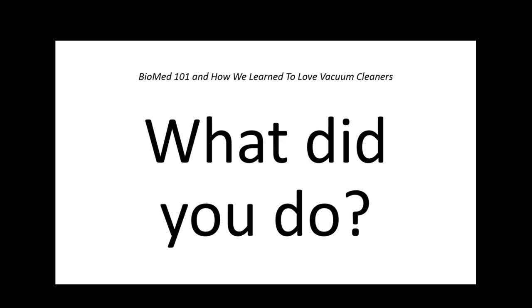We're big on the dispensers, the liquid and rag dispensers, the purple tops and the gray tops. And they're running short. They've been running short since COVID came out. It's hard to get those things. Those were pretty benign on a lot of equipment. They killed stuff, but didn't kill the equipment too. And so they're running out of that. They're starting to use some stuff that attacks plastic.